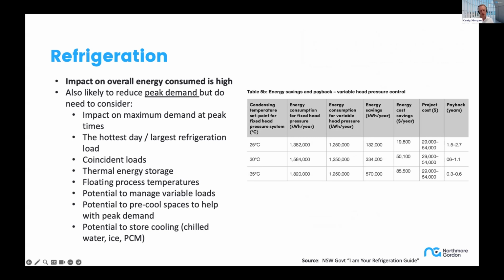So in sizing though, or working out, particularly in a refrigeration system, how much peak demand you're going to reduce, there are some important things to consider. It is different than compressed air because maximum demand can occur on that refrigeration system at peak times, on the hottest day with the largest refrigeration load at times of highest production. So then you can go beyond that and say, well, what coincident loads are happening at that time? Can we manage them? Can we look at thermal energy storage? And in this case, I'm not talking about hot energy storage, I'm talking about cold energy storage.